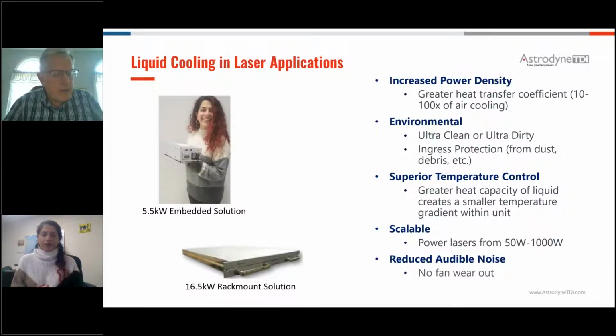Sure, Tamanna. Astrodyne TDI has had well over 30 years of experience dealing with liquid cooling. It started out with military applications way back when, but that's evolved into industrial, medical, and aerospace applications that we use for liquid cooling. Liquid is a much more effective means of removing heat, well over 10 times the ability to remove heat than air is. So you get better heat transfer, and if you're effective at your design, you can realize improved power density - less volume for a given amount of power to support the power conversion requirements.